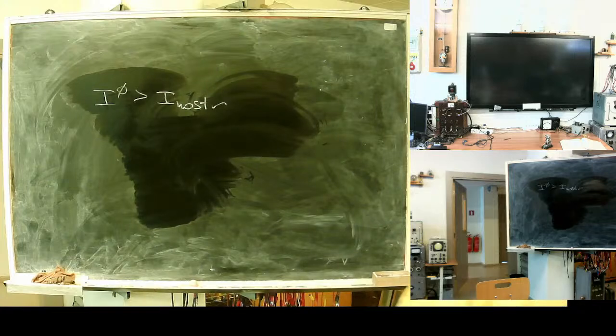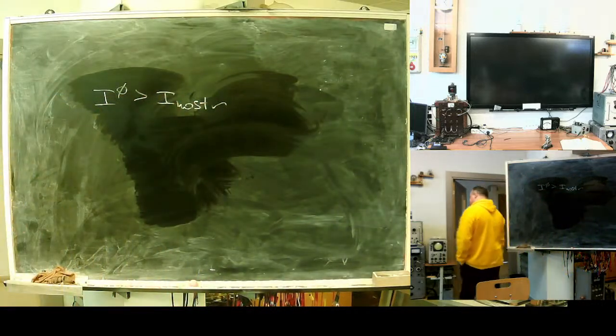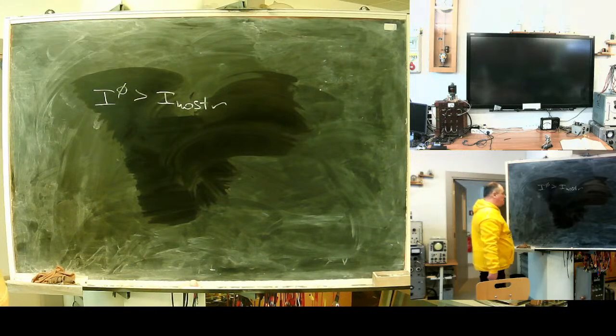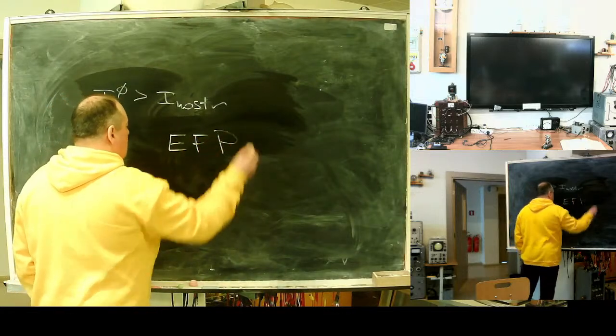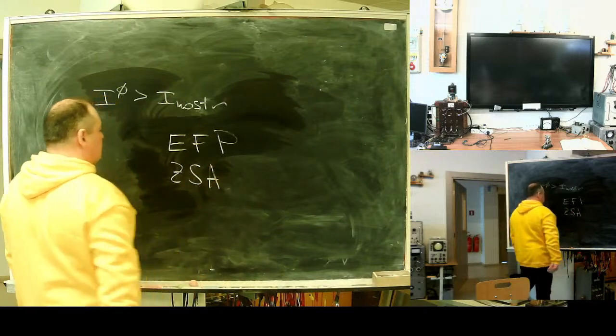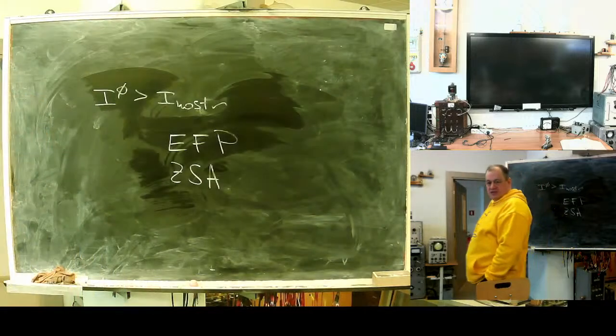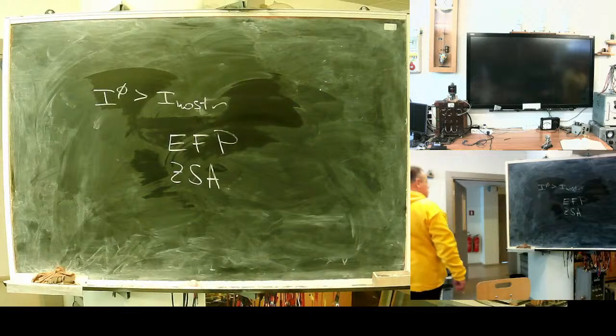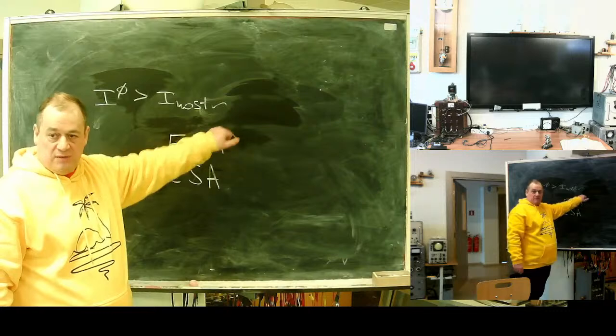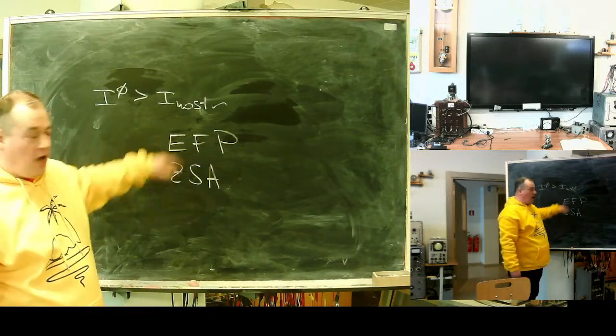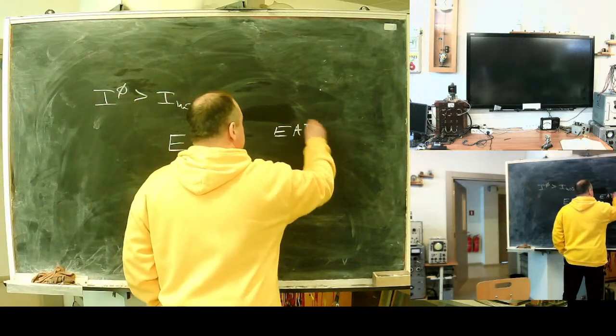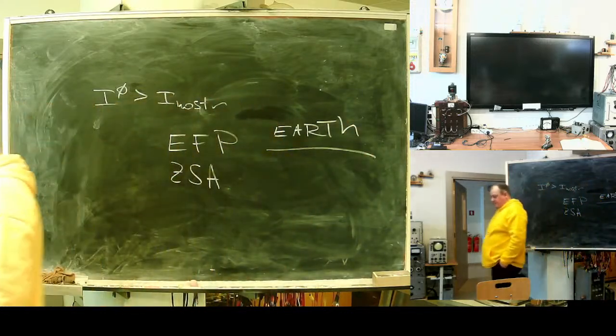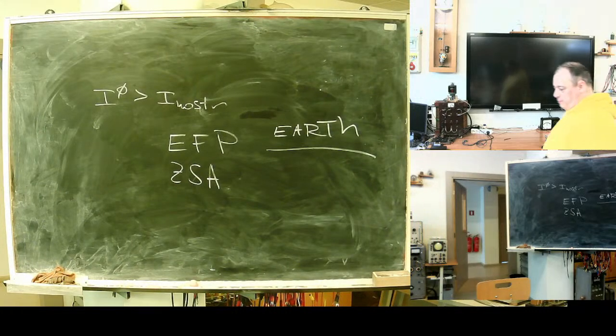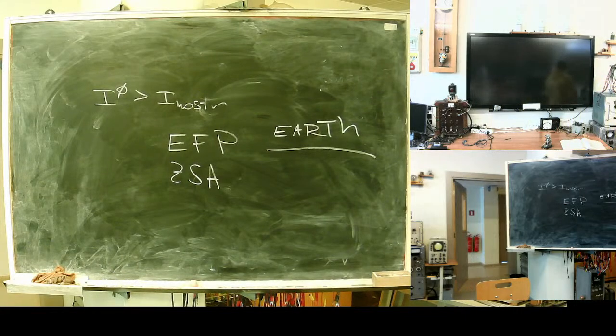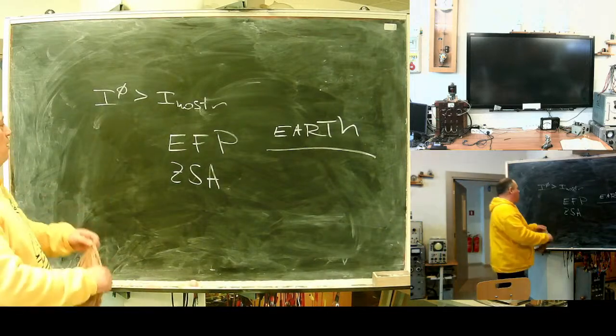Zero sequence current. You need to know what a zero sequence is. So, zero sequence current. EFP, earth fault protection. In Latvian ZSA, Zemes slēguma aizsardzība. Zeme is earth, slēgums is fault, aizsardzība is protection. So EFP, it's an earth fault protection. What's the meaning of E? Earth, E-A-R-T-H. Earth fault protection operates on zero sequence current. Earth fault protection.